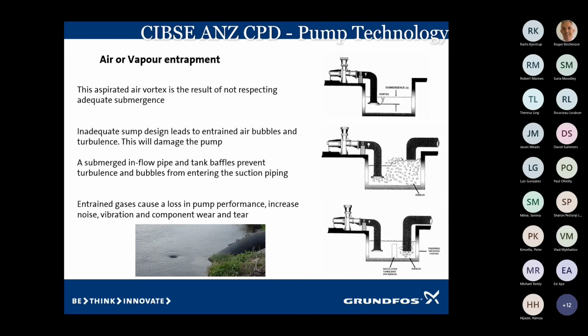To overcome both those, we can put baffles in. So the top diagram, you would put a baffle on the water, and the baffle would be much wider than the diameter of your intake pipe and stick out quite some distance. That way, the vortex can't be pulled down from the surface. It can only draw the water from around the intake. The second box, what we can do there is like we have on the bottom, is put a vertical baffle in. So now the water is entering into the stream, into the water. The discharge pipe into here is lower, and the air bubbles can actually come up and then escape to the atmosphere, and then the water is pulled across into the next pit, and then it is pulled away from there.